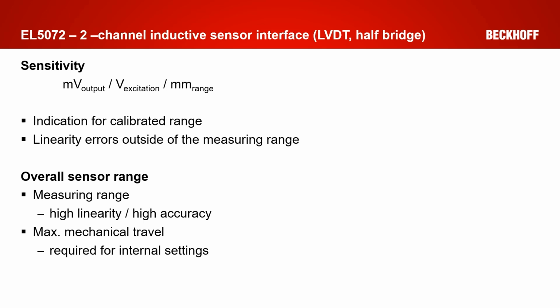The calibrated measurement range is usually smaller than the total travel way of the probe. In the measuring range, the probe has the highest linearity and therefore also the highest accuracy, while the mechanical travel is determined by the mechanical setup. The specification of the maximum travel distance is needed internally to determine the maximum voltage that can be measured back. If you put in too low a value here, some errors can occur because the measured voltage is higher, and therefore it will internally lead to an amplitude error.